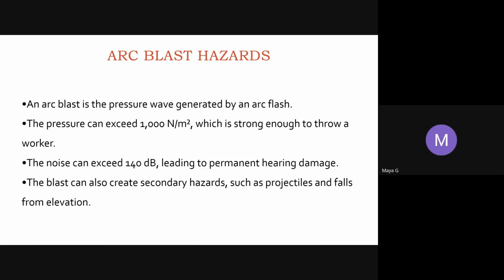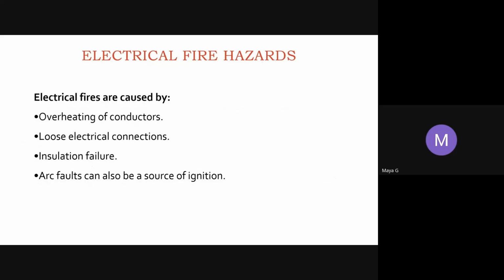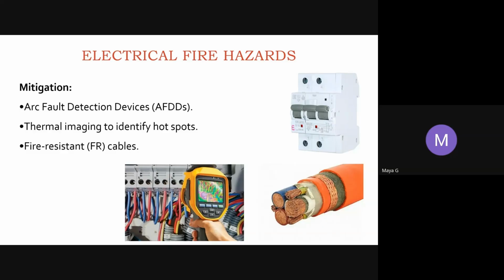Next is arc blast. The arc blast is the pressure wave generated by an arc flash. As I said, the pressure will exceed 1000 Newton per meter square, and it will throw the worker away, and the noise can go beyond 140 decibels. Next is the electrical fire hazard. Electrical fire hazards are caused by overheating of conductors, loose connections, and insulation failure. An arc fault can also cause ignition. The mitigation devices for electrical fire are arc fault detection devices, AFDDs, thermal imaging to identify hotspots, as we can see in the picture, and fire resistant cables.